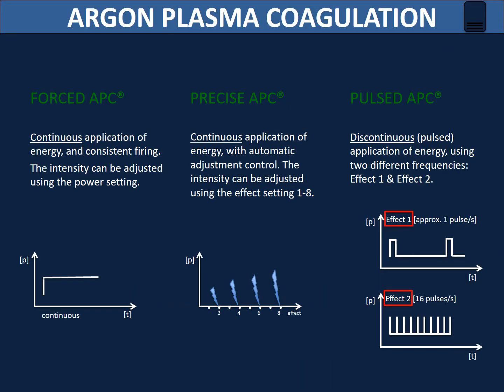The argon gas flows down through the scope catheter, which contains an active electrode connected to the ESU, and delivers a monopolar electrical current, converting the inert argon to ionized argon gas, which is called argon plasma. The ionized, electrically conductive argon gas can cause tissue coagulation via three distinctive modes with different coagulation properties.